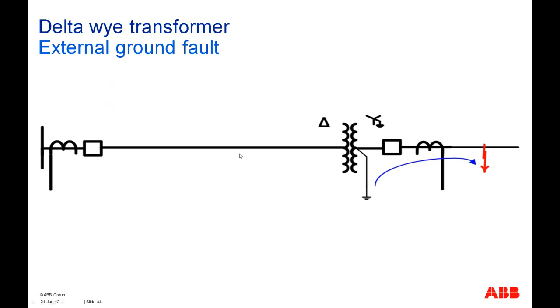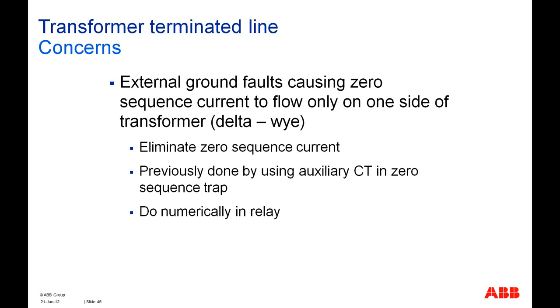Similarly, if we have a delta Y transformer and we have Y grounded on this side of the transformer, then any ground fault on this point would result in zero sequence currents, which will circulate in this direction and will be felt only on the remote side, but not on the local side of the line differential protection scheme. Therefore, we need to do this zero sequence current elimination to avoid this kind of situation. Previously, it was done by using auxiliary CTs, but now it is done numerically, because all these numerical relays can calculate these currents in the proper way.